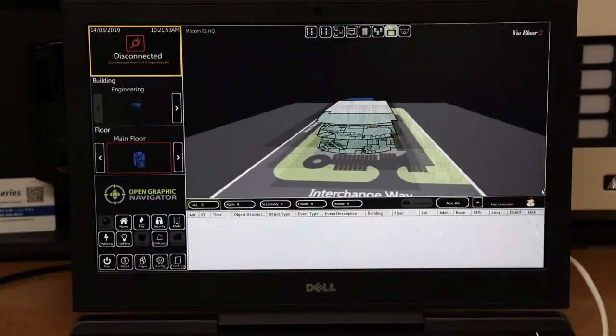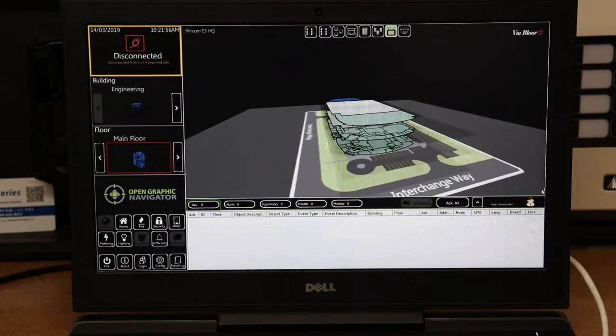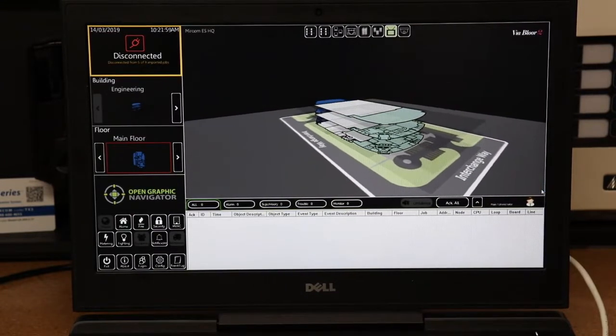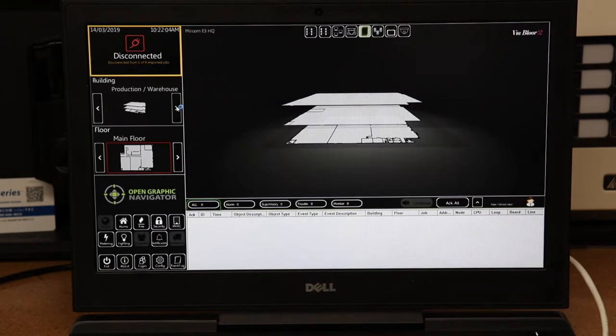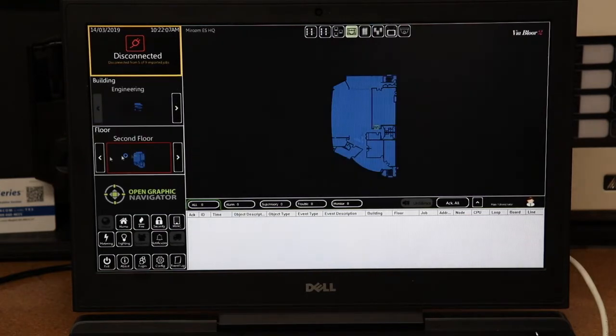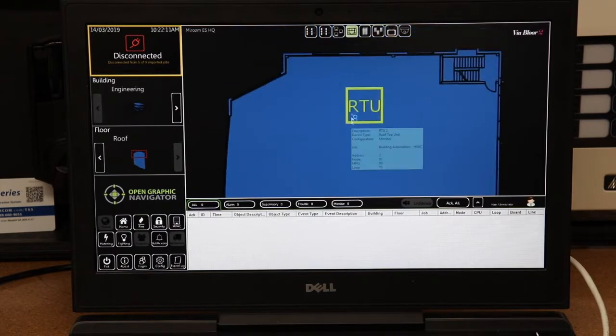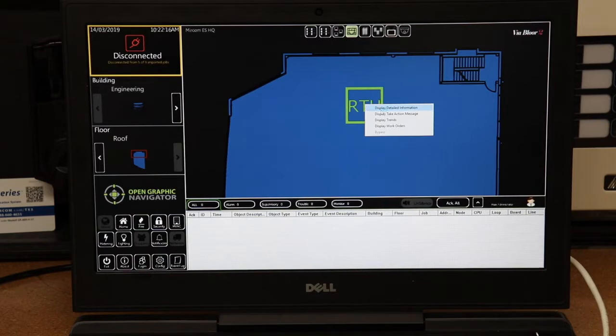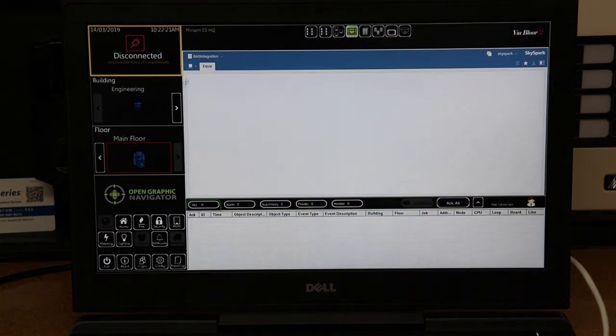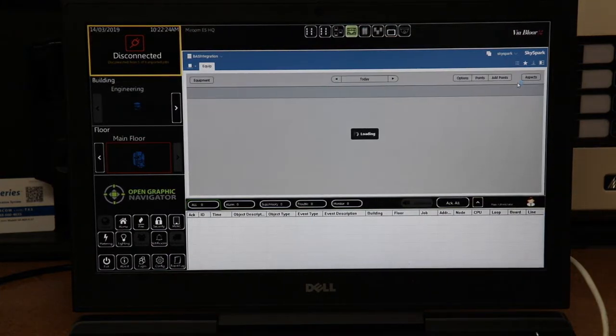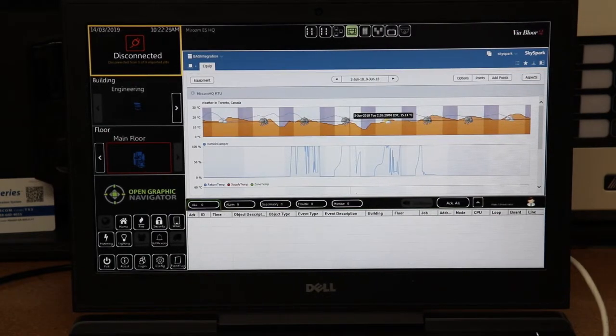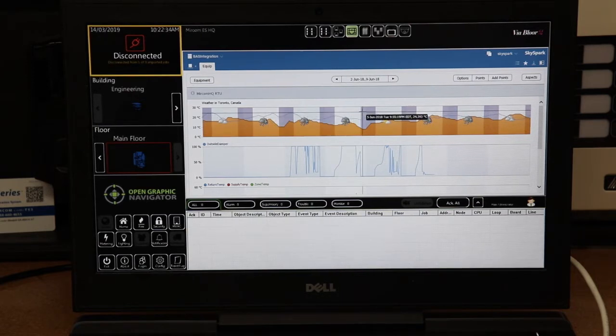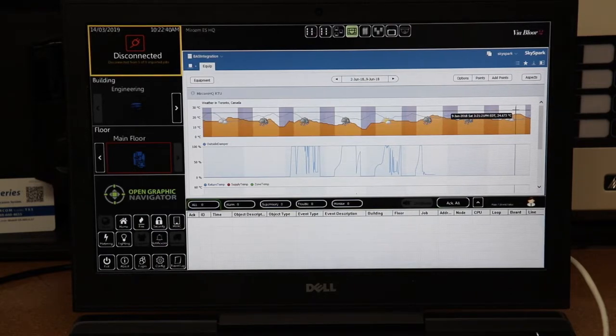One of the most interesting tools that we've incorporated into OpenGN is the ability to pick up a web view of trending analytics data coming in from some other source software. So in this case here, I can navigate to my HVAC equipment on the rooftop of the engineering building. And when I zoom in to my device icon representing my rooftop unit, from the right-click contextual menu, instead of viewing the detailed information, in this case I'll pull up the trending data. What you can see here is that we've embedded real-time data over a period of time that will present to you things like the outside air temperature for the past day, week, or month, also presenting information about the set points within the system, and this allows you to do some advanced data analytics on top of the SQL Server database which is native within the OpenGN.